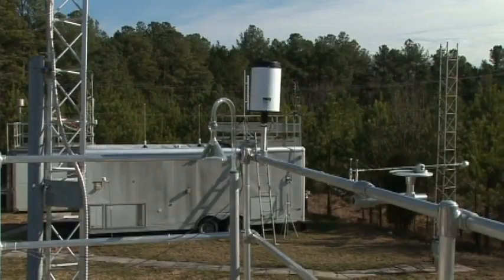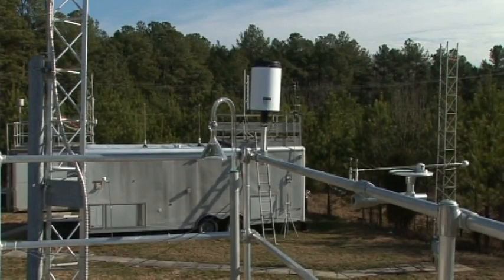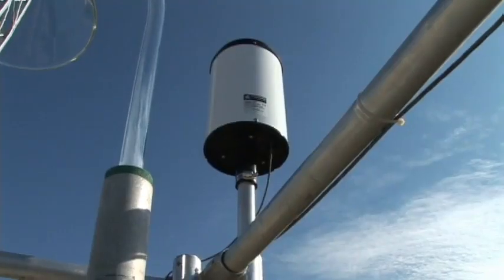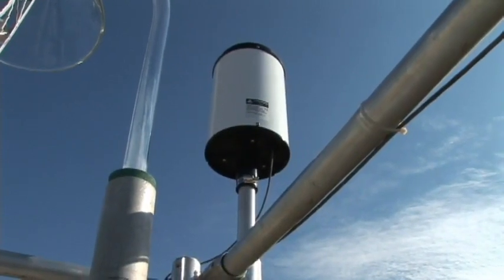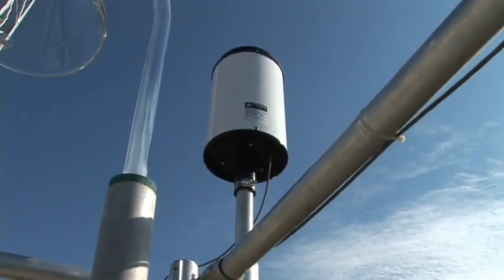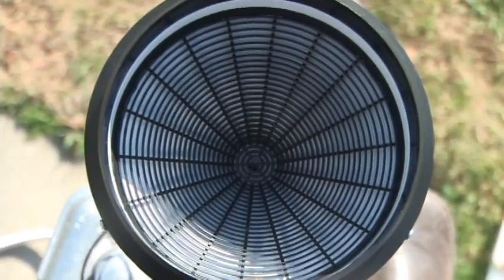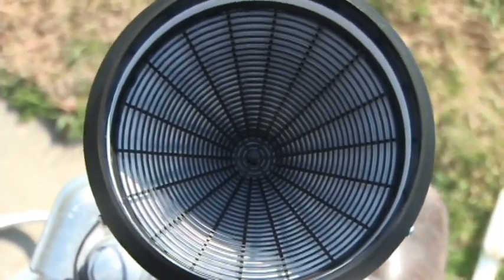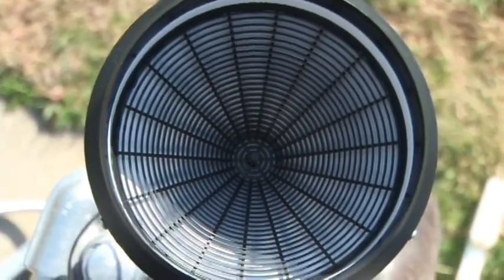This sensor is an R.M. Young Corporation Model 52202 tipping bucket rain gauge. It is attached to the railing of the top of the monitoring shelter. Note that the opening of the rain gauge has a conical shape. The opening is sometimes known as the pan or the funnel of the gauge. The funnel is designed so that strong winds will not allow rain captured in the funnel to escape.